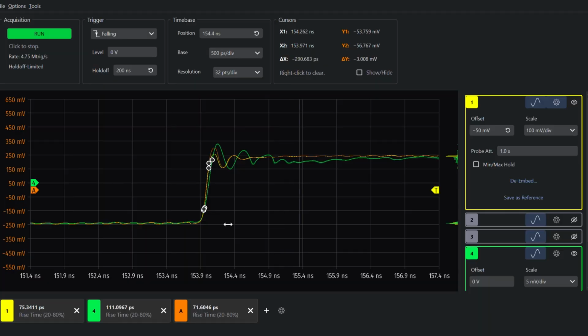So here we have our three traces. We have the original unloaded signal generator trace in orange, the loaded signal generator trace in yellow with the probe attached, and the probe response is in green. So first of all, let's look at how the signal generator is loaded. We can see that there's a very small change in peaking there, and we can also see that the rise time of the signal generator has increased from 71 picoseconds to 74 picoseconds, around a 3 picosecond increase. So really, this signal is barely being touched by the addition of this probe, a very subtle set of changes there.